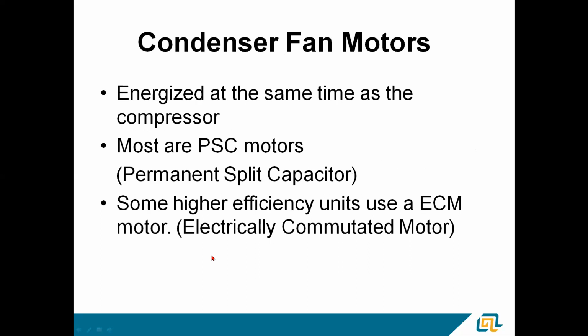Just a little bit about condenser fan motors. We're just about done here, gentlemen. Of course, it's energized at the same time as the compressor. Most of them are permanent split capacitors or PSC motors. Some of the higher efficiency units will use an ECM motor, the electrically commutated motor. That's on the higher efficiency units.